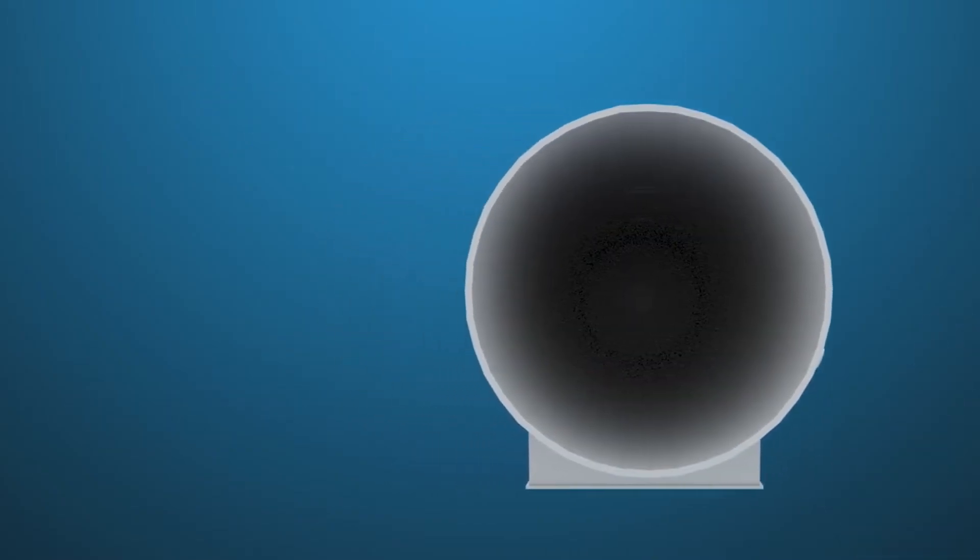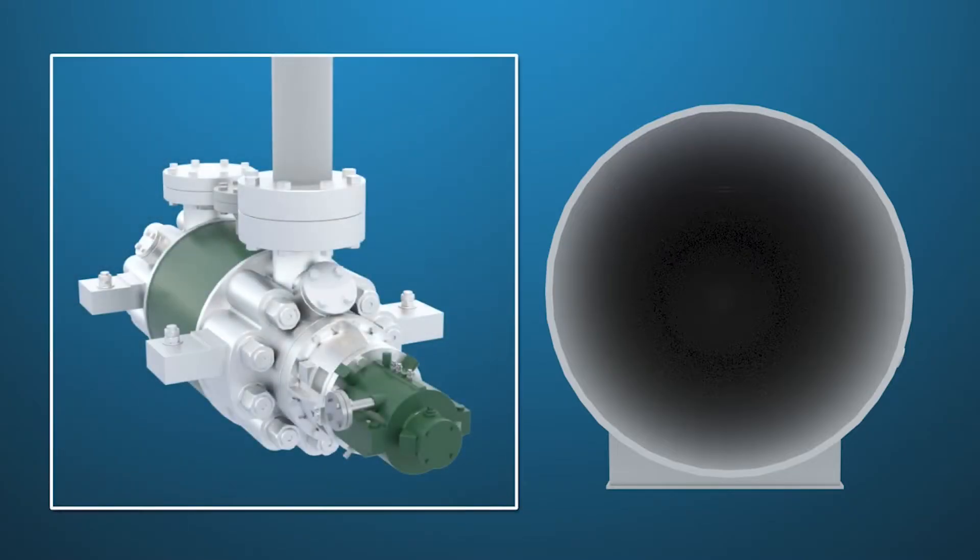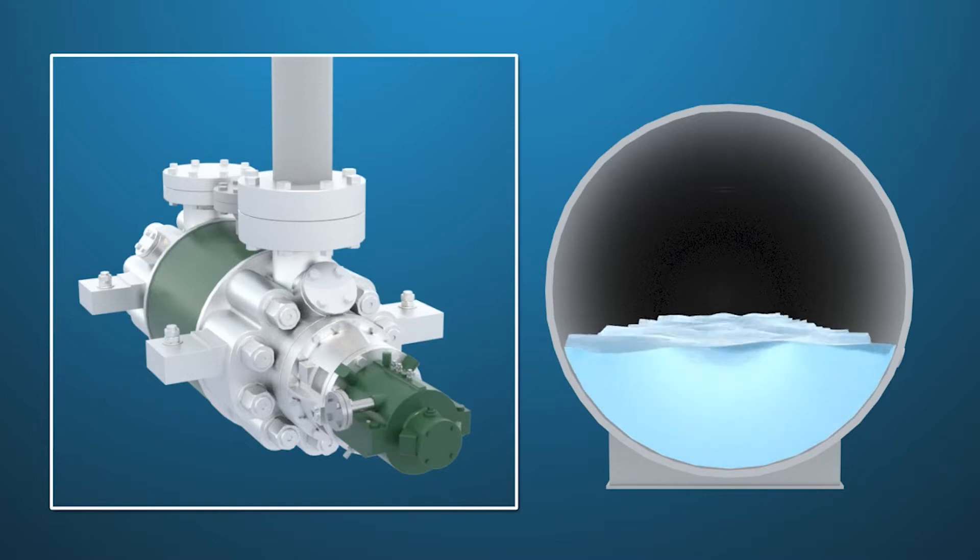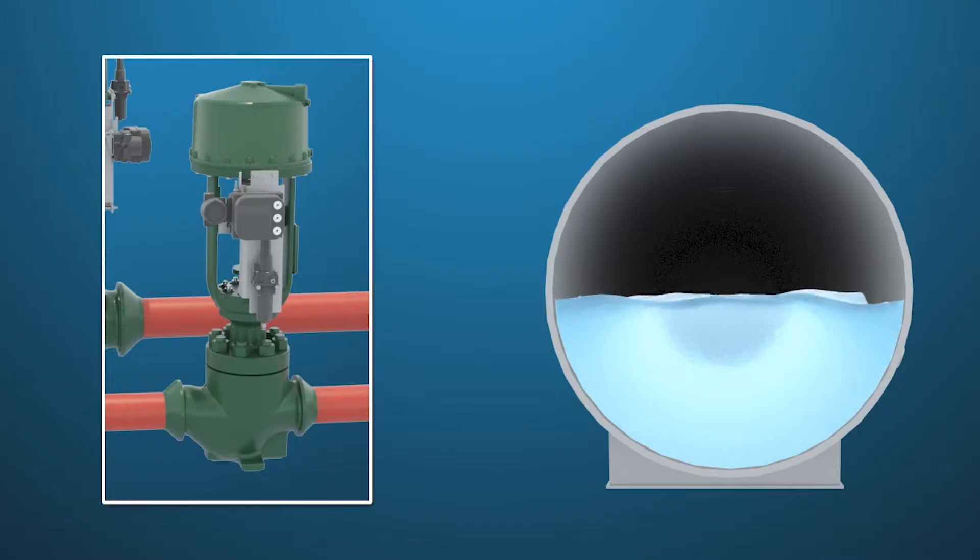When the drum is empty, the pressure inside is atmospheric. The boiler feed water pump will be at high discharge pressure, creating high differential pressure that can cause cavitation in the valve. The startup valve needs to be designed to eliminate cavitation damage.